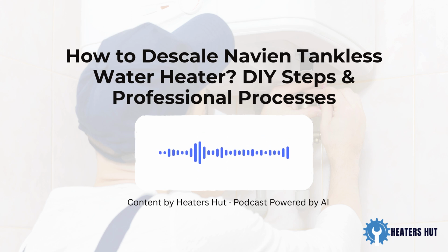More usage means more water and therefore more minerals passing through the system. So what's the general guideline? Navien generally recommends descaling at least once a year. That's the baseline, but you need to pay attention to your own situation, using factors like water hardness, temperature setting, and usage to gauge it.